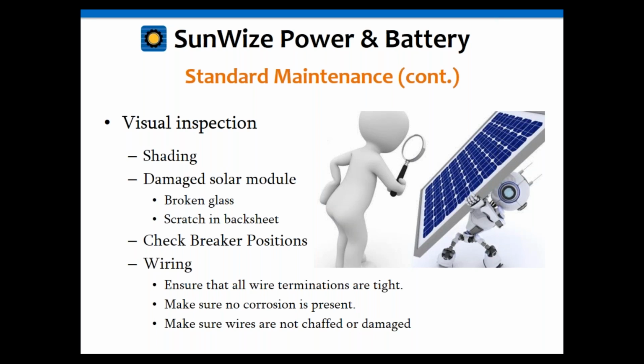People always ask, why do you have to check for the terminations? If they're tight, they're tight. But what ends up happening is that thermal cycling causes them to loosen over time. As metal expands and contracts, which happens through normal cycles, depending on where you are in the country, you might find the temperature varies by 20 degrees a day or 30 degrees a day or even more. And that delta in temperature causes the metal to heat up and shrink, and heat up and shrink. Although it may not seem like much, over the course of years, that can be enough to loosen a connection, and it can cause all kinds of issues at that point.